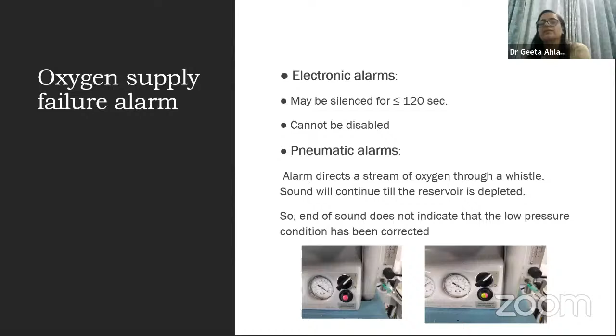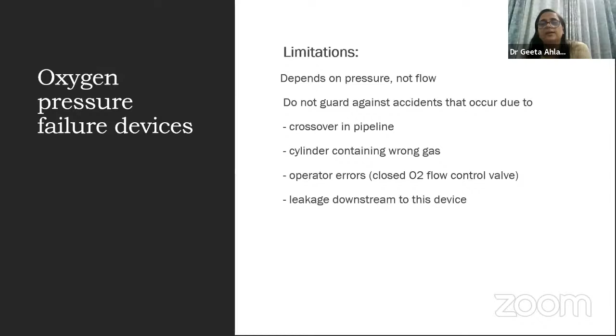So these oxygen devices are really helpful to us, but still they have their own limitations because they depend on pressure and not the flow. They don't guard you against accidents if there's a pre-mixing, if the cylinder of oxygen has been wrongly filled, or the pipeline of oxygen has been crossed over by some other gas. Then there are operative errors and leakages downstream to this device. But still, whatever we have is our best guard, and we should check and have these in proper place.